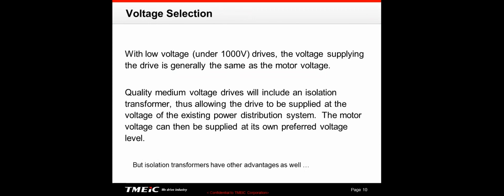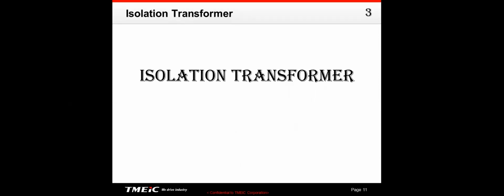It is very, very common to have the voltage going into the drive be different than the voltage coming out of the drive. And so when we go to a medium voltage drive, we don't just say, hey, I need a 4160 volt drive. The question is, what voltage is your motor and what voltage is your power system? And we can have a different voltage coming into the drive than going out of the drive. Now, one of the reasons for that is that most medium voltage drives will include an isolation transformer. This is point number 3.